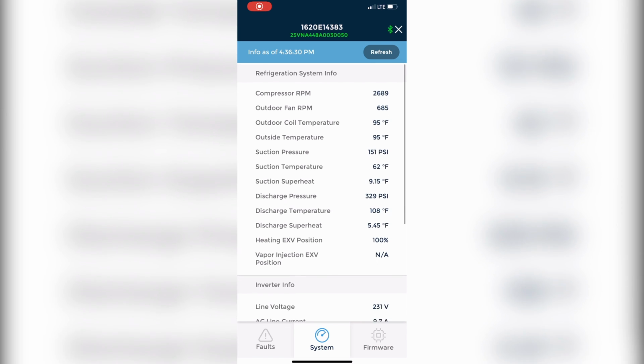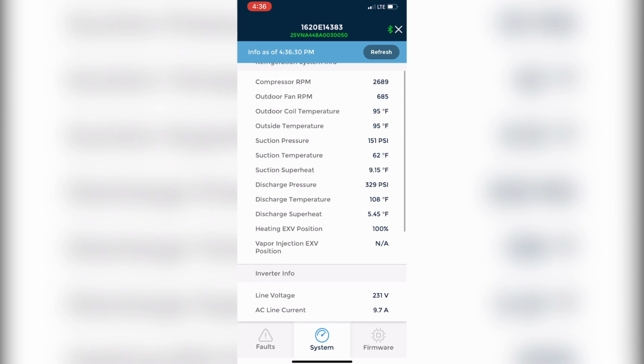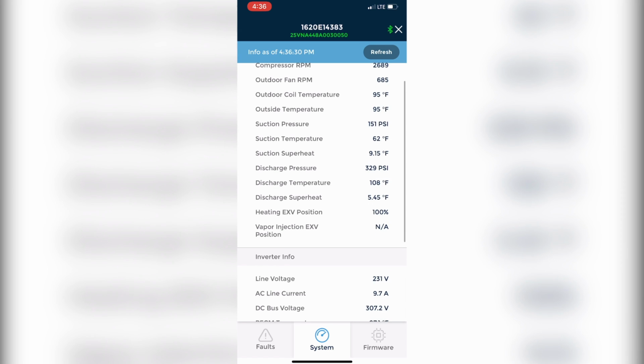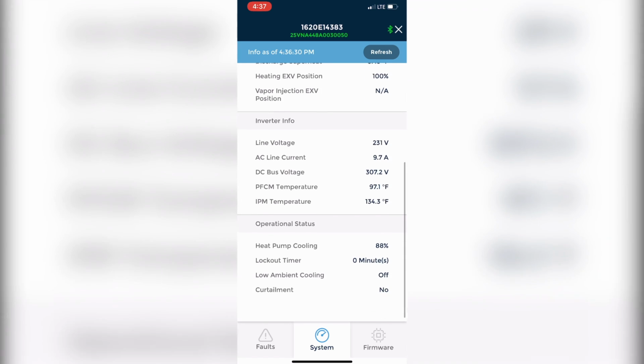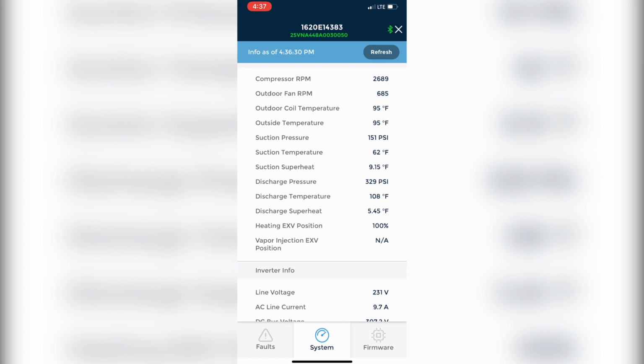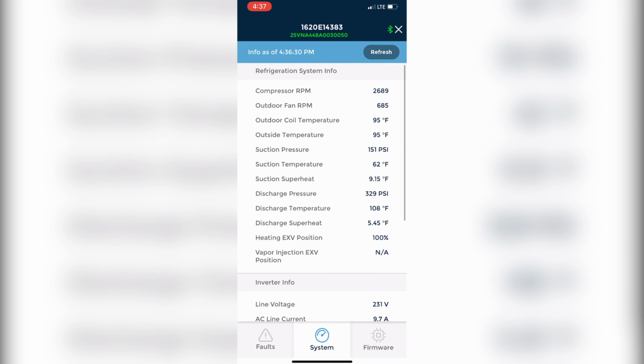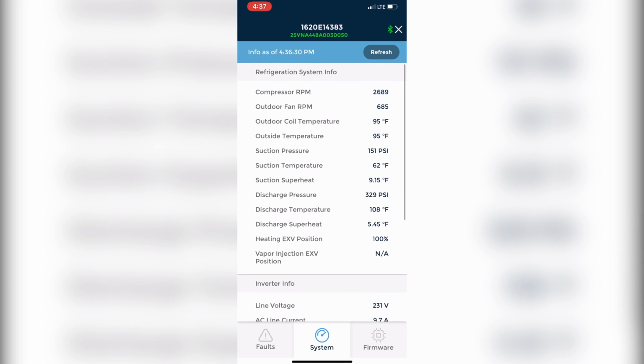All right, so we've got it in test mode. We're running it up in high load and testing everything out. We're also taking our own measurements outside to verify. Our superheat looks good. We're going to confirm our subcooling using Measure Quick. This is actually through the Carrier Tech app.